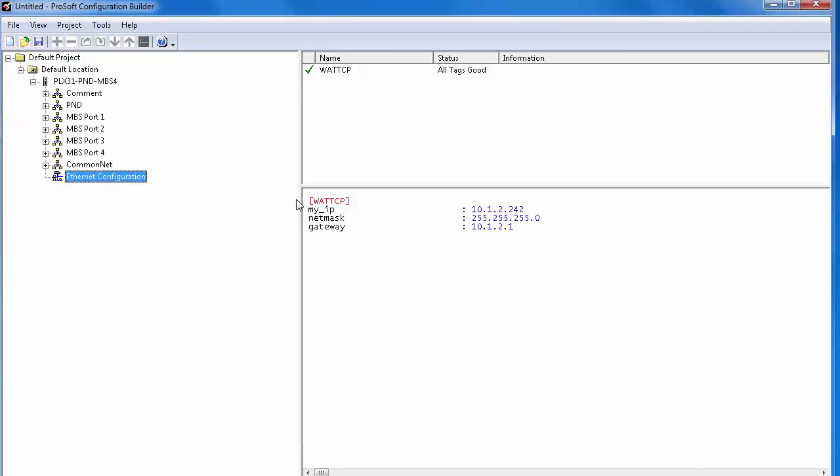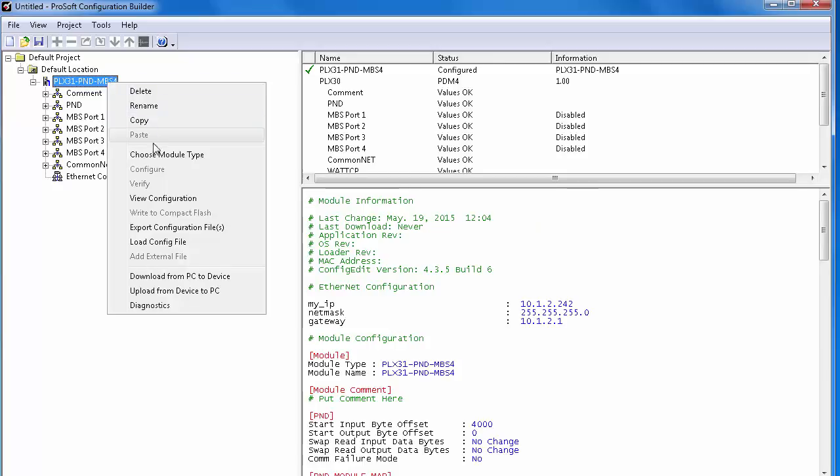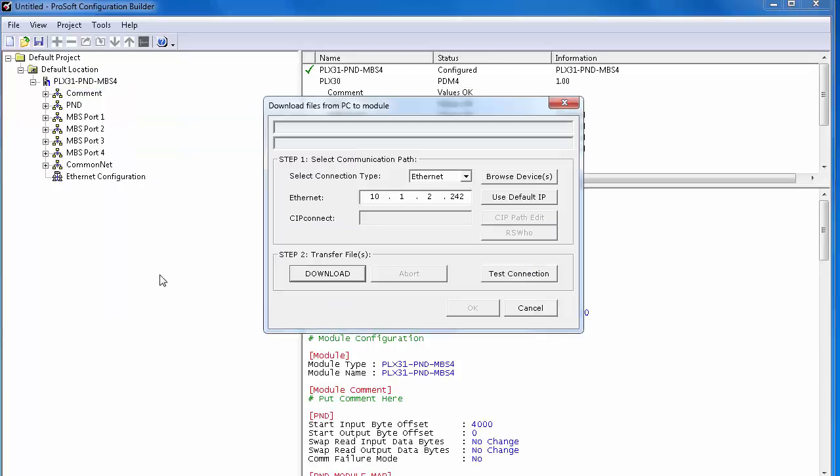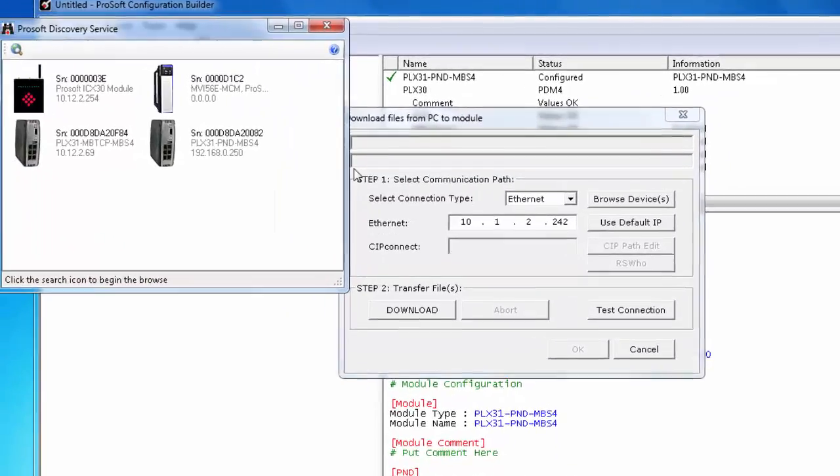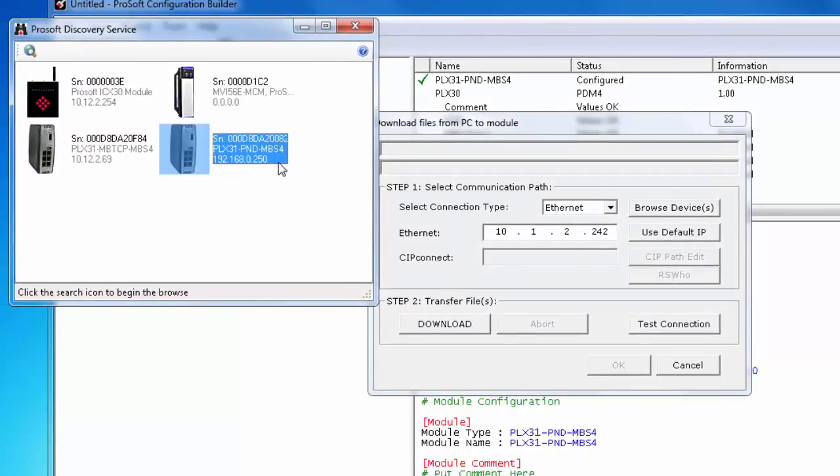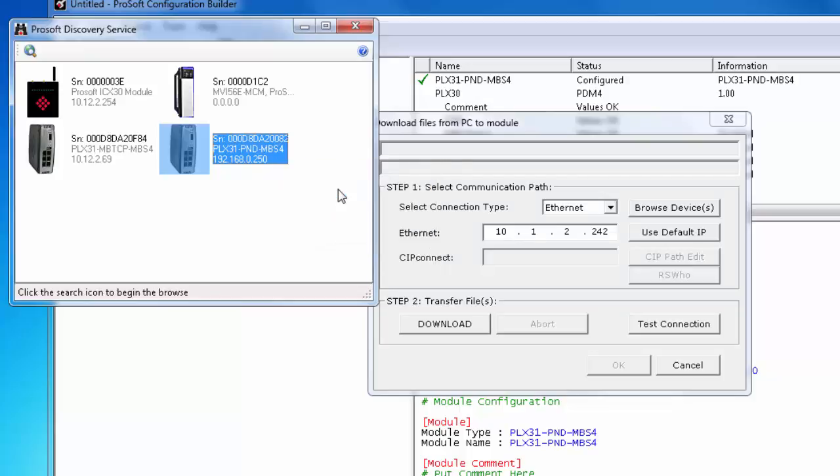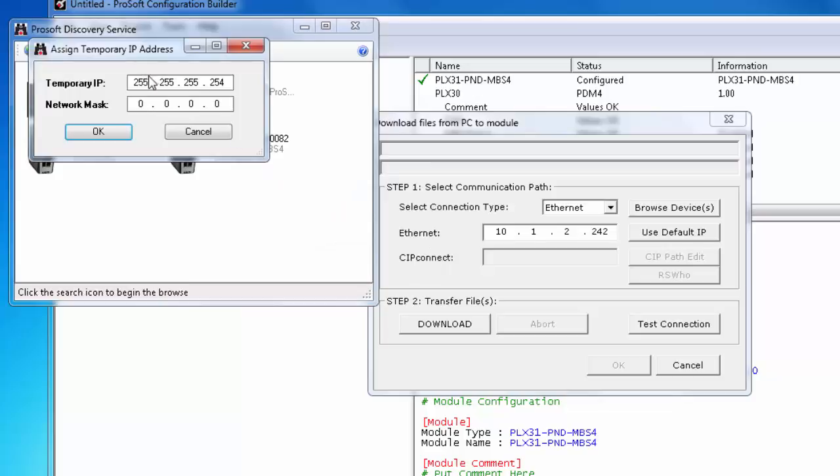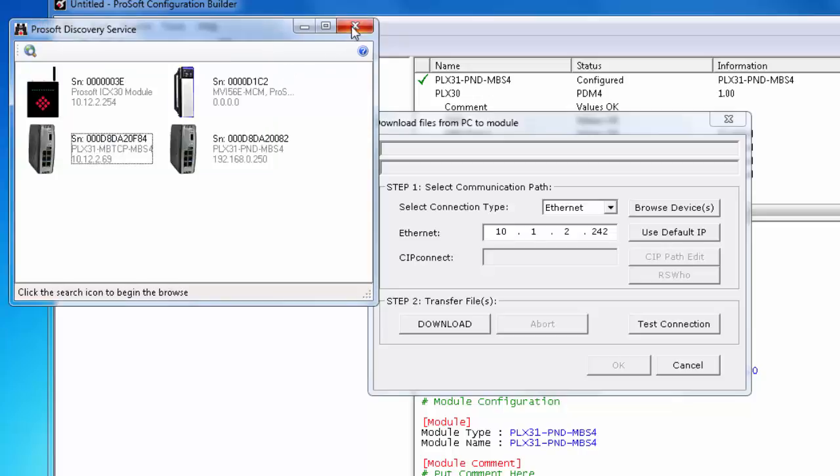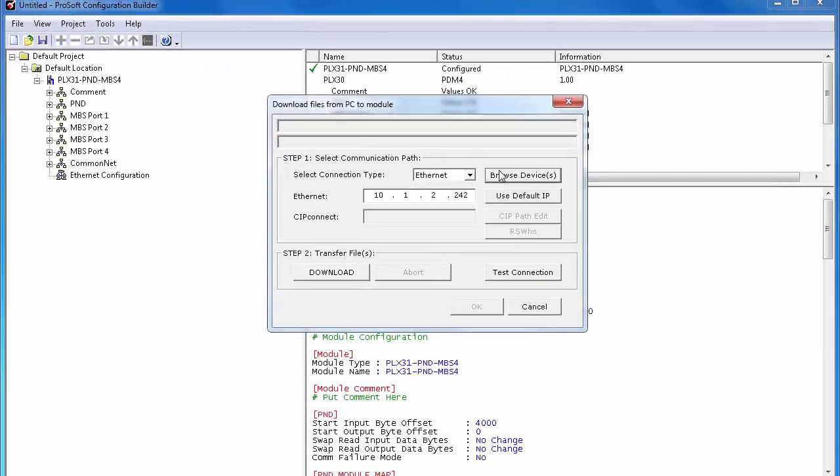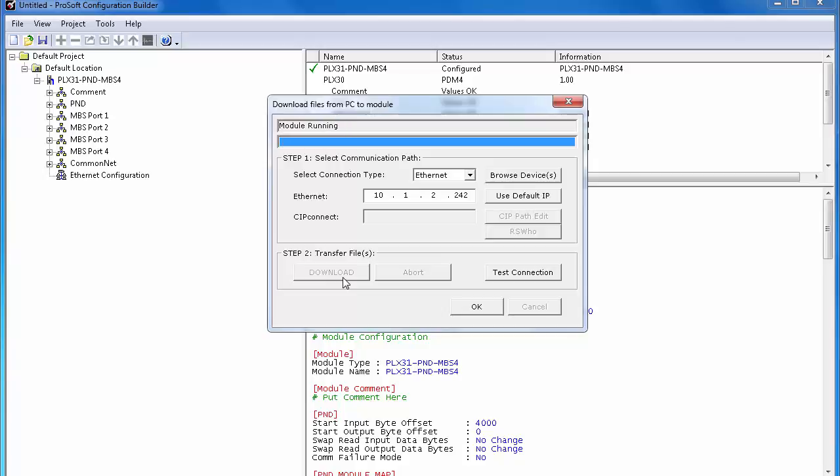Even though the module has a default IP address that's not on our subnet, we can still download to it by giving it a temporary IP address using our ProSoft Discovery Service. Right-click on the module, choose Download from PC to Device, and once this opens, choose Browse Devices. In the new window, you'll see your PND MBS gateway along with any other gateways on the network. Right-click on it and choose Assign Temporary IP. Type in the address you entered earlier, since we know this address is available. For me, it's 10.1.2.242.